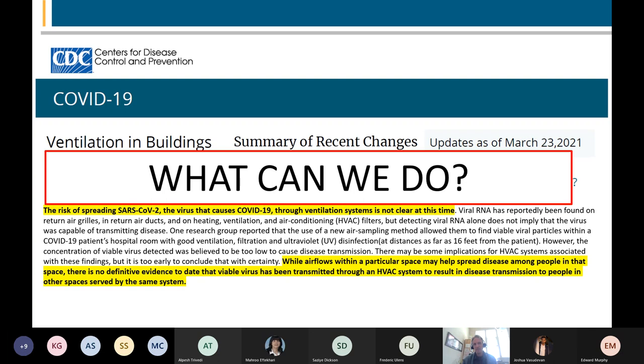Now, with a HEPA filter, for example, and most other MERV filters, the most penetrating particle size is somewhere in the area of 0.3 micrometers. But based on the methods of filtration that occur, and there's an array of them that impact a filter's ability to extract a particle, that 0.3 most penetrating particle size is the hardest particle size for that filter to extract. That's where you rate its efficiency. So a HEPA is 99.97% efficient at extracting particles at a most penetrating particle size of 0.3 micrometers. It can more efficiently extract both larger and smaller particles. And it's just based on the methods of filtration.